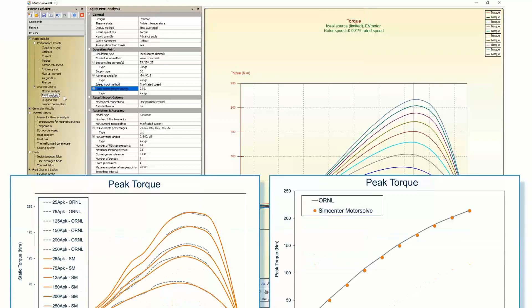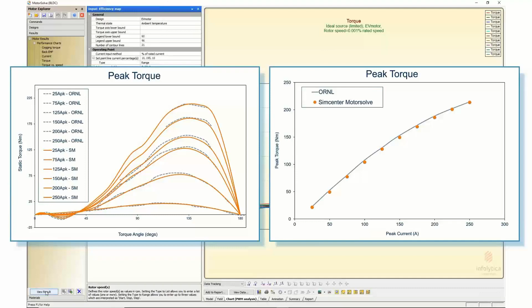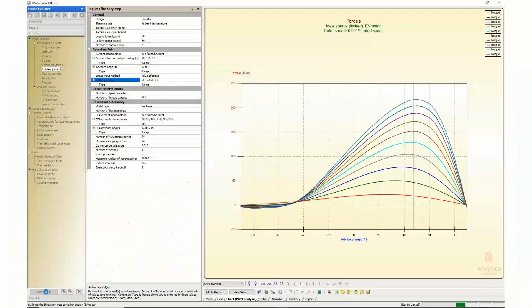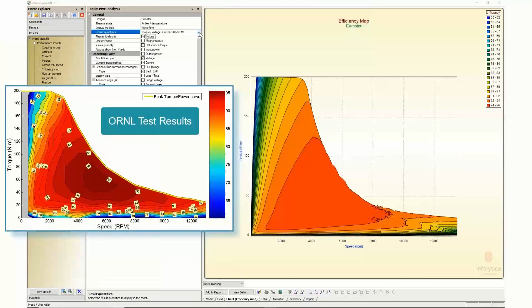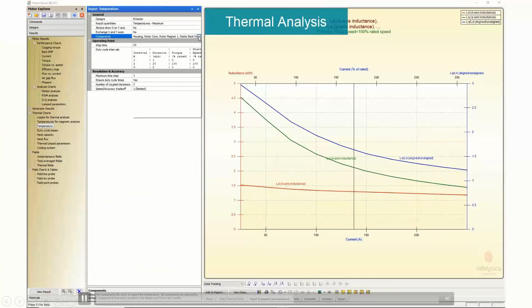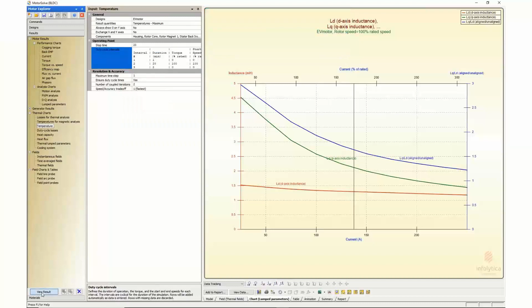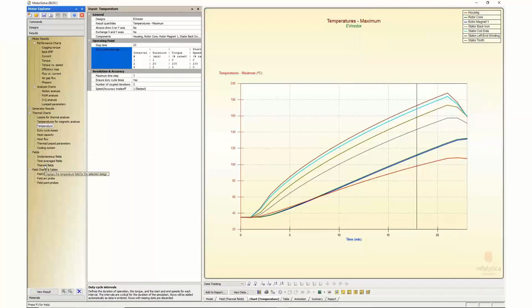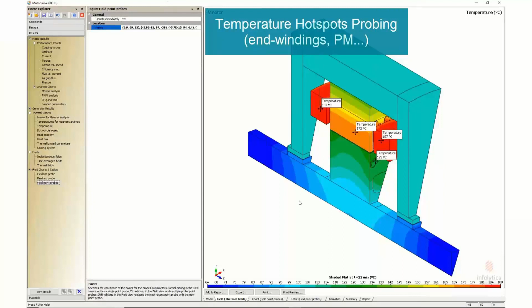It's also important to ensure that the motor meets the target peak torque demand and the torque speed operating envelope is within the associated efficiency for the motor. And then as well, for the specific drive cycle here, we can look at the temperature evolution of the motor. And we can look at the various temperatures for the different motor parts given the drive cycle in here and the motor itself, and then look at probing the 3D temperature field to quickly identify the hot spots in the motor. And here we can see these are the benefits of doing a more 3D analysis.